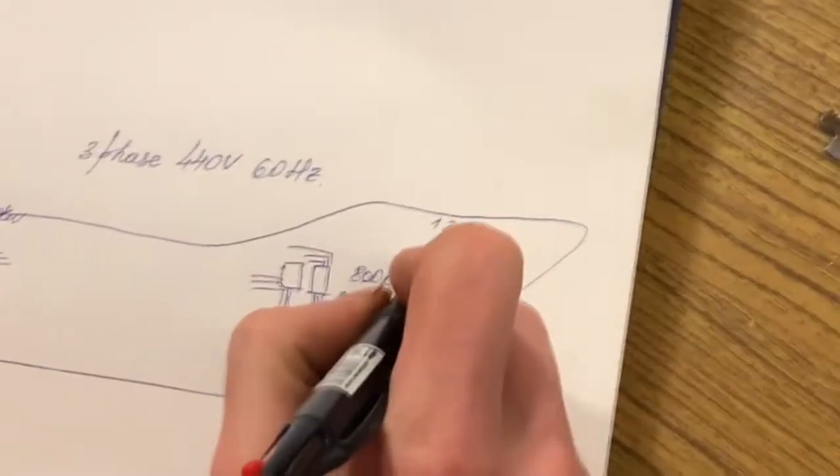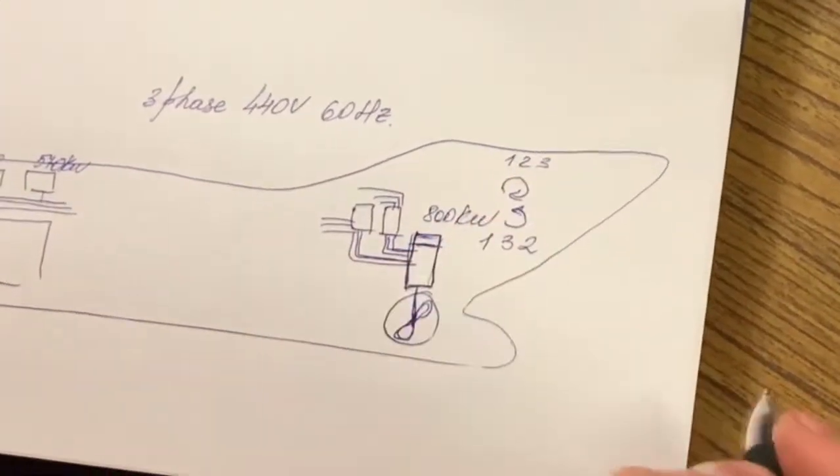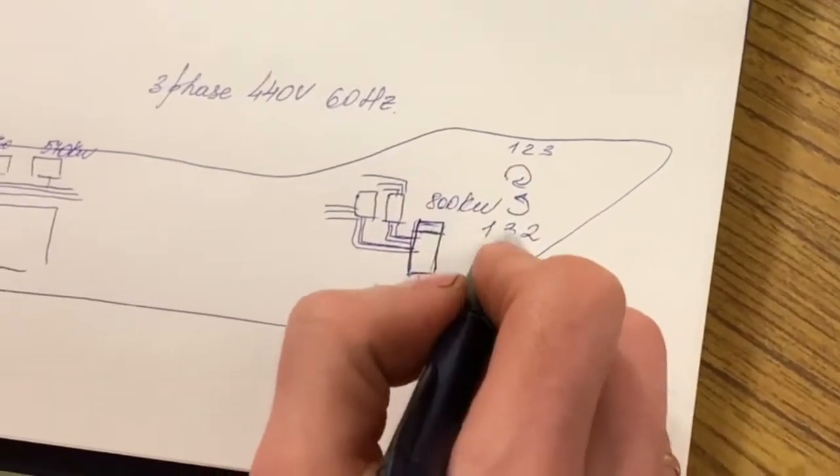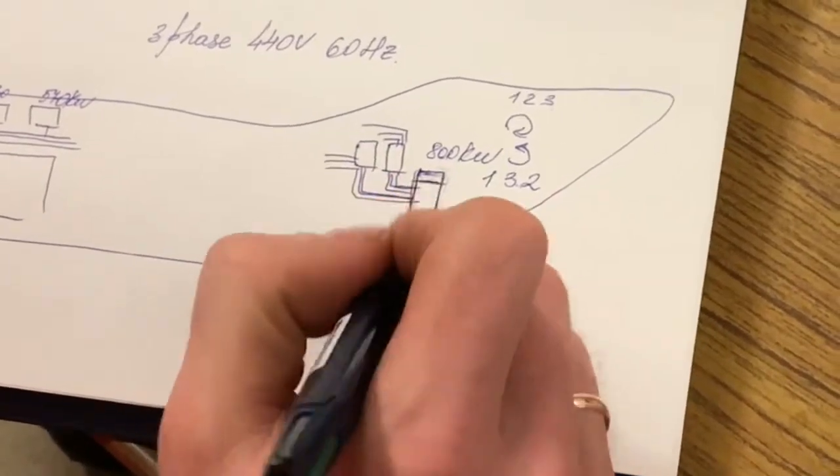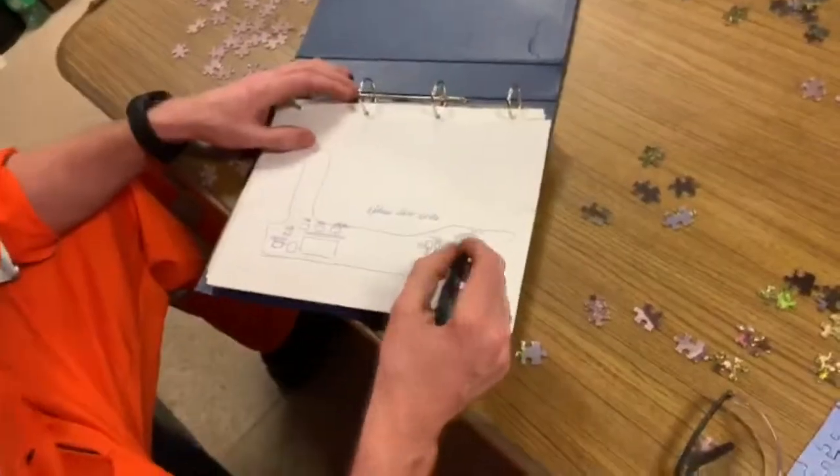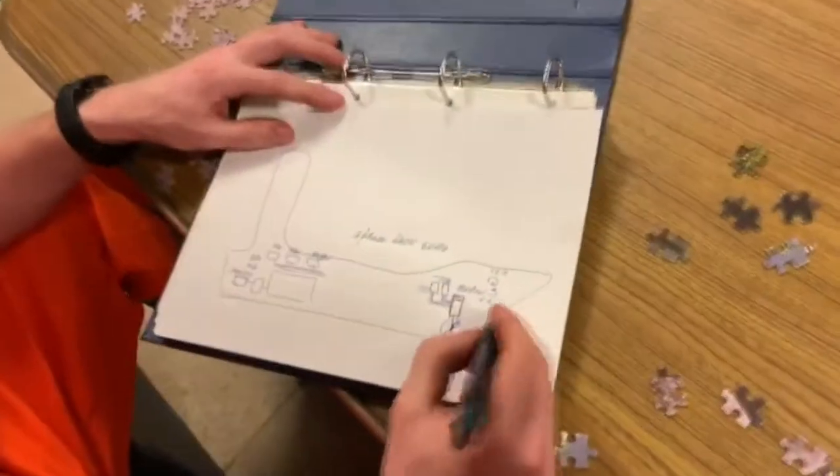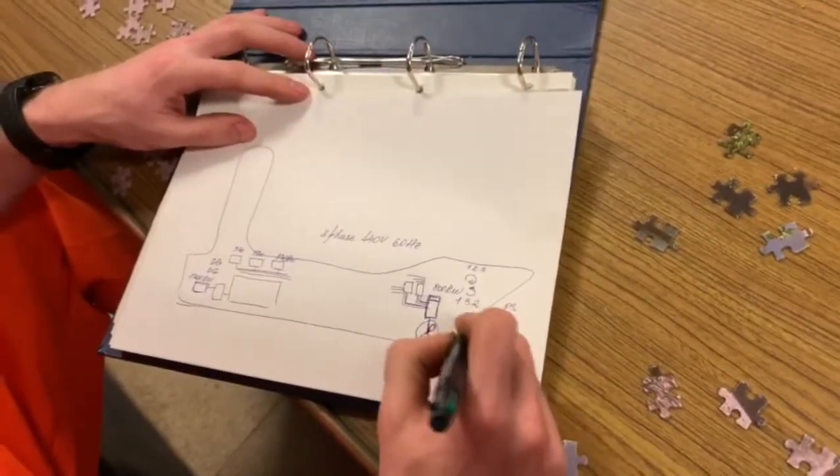If you want to rotate it counterclockwise, it will be one, three, two. So connected a bit different. So if you are changing one phase, the motor starts rotating in the different way. And when the electric motor starts rotating in the different way, it is moving port side or starboard side.